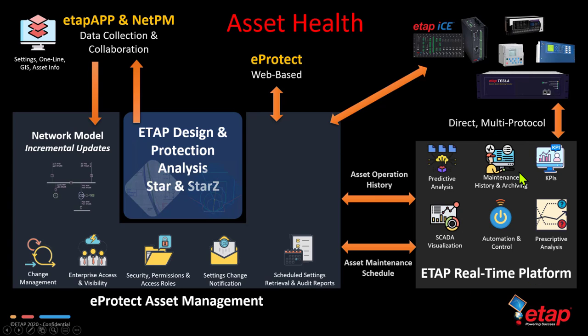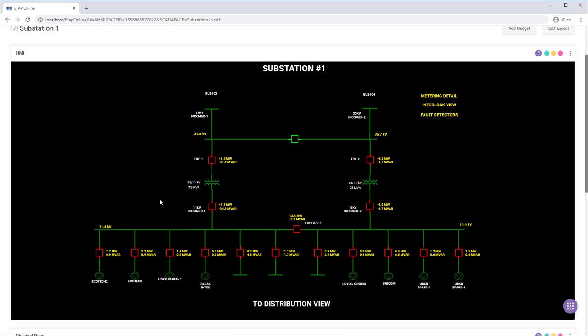However, the ETAP real-time platform is optional, so eProtect can communicate with all of these devices directly, allowing you to retrieve information such as fault waveforms and the relay settings directly from these devices. Our substation SCADA view is graphically customizable, so users can configure the view to their preferences. Any details from the substation can be configured, brought in, and mapped. The tags can be mapped over and monitored. Currently, we're looking at real power and reactive power associated with various meters on the network, as well as bus voltages. We are not limited to just these measurements. Any measurements available through the telemetry in the field can be displayed.